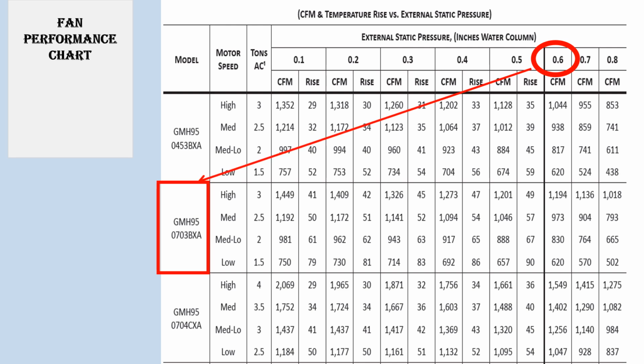If we look here, we find our fan performance chart. We get our model number, and we look at our chart, and we're at 0.6 static. So right now in high, we would have 1,194 CFM for a 3-ton unit. And if you notice, on each column up to the 0.5 static limit, it has the rise as well. So whatever airflow you look at, you look at your temp rise, and you'd be able to find out what CFM you would need to keep that temp rise.